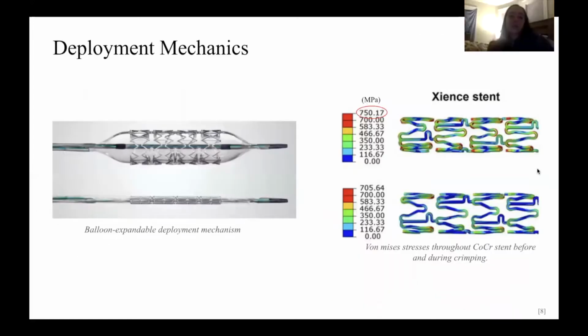So our design will incorporate the balloon expandable deployment mechanism. We looked at stresses produced during crimping of the valve. The image on the bottom right compares variation in von Mises stresses throughout a cobalt chromium stent during crimping, with maximum stress throughout the stent being 750 MPa, which the valve will need to withstand.